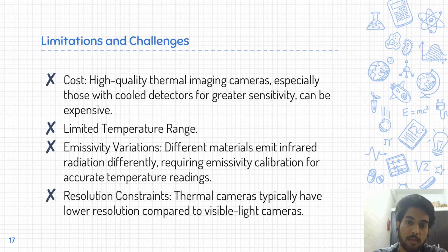Now let's discuss some limitations and challenges. The cost is a limitation, because high quality thermal imaging cameras, especially those with cooled detectors for greater sensitivity, can be expensive. Because these thermal imaging cameras are used to scan hot surfaces and hot areas, in order to maintain proper operating temperatures for the instruments inside the camera, oftentimes they are required to be cooled, and this whole setup to keep the camera at a certain temperature can be a little costly.